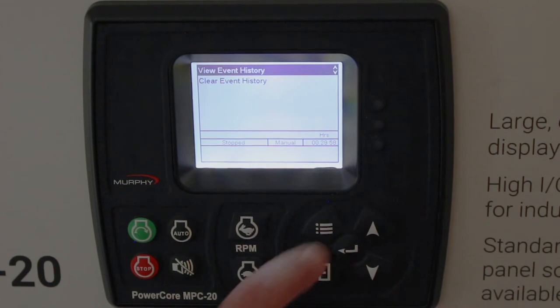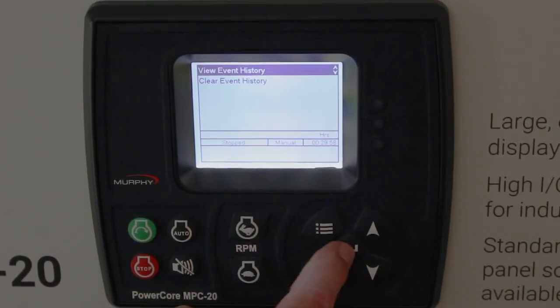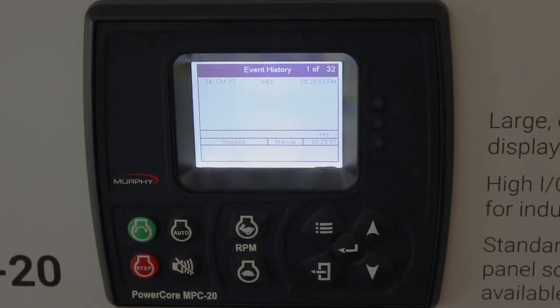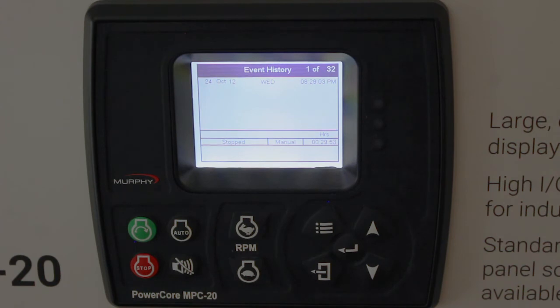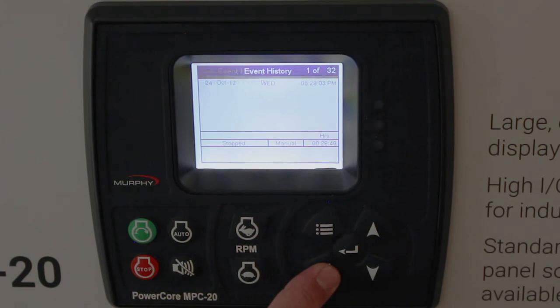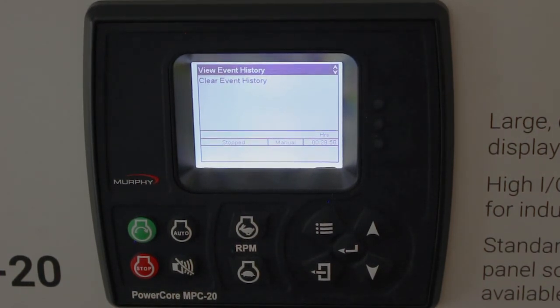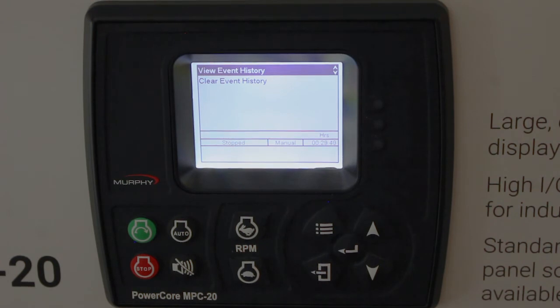Event history — you can view the event history and clear the event history. We've got a few events from me using it. It stores up to 32 events. You can clear it if you want, and it date and time stamps everything. It's handy if there's a problem at the site or it keeps going down on a shutdown and you're not sure what shutdown it was — you can look at the event history and it'll tell you the date and time it went down and on what shutdown.